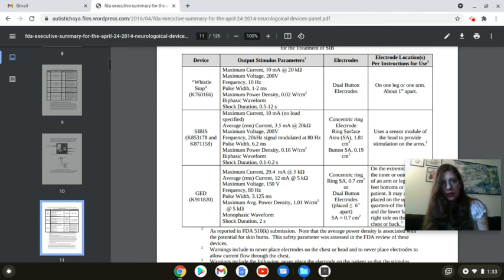Average current, we just went over that, sorry. Maximum voltage 200 V. Frequency 20 kHz, signal modulated at 80 Hz. Pulse width 6.2 ms. Maximum power density 0.16 W/cm². Biphasic waveform, shock duration 0.1 to 0.2 seconds. Uses a sensor module on the head to provide stimulation on the arms.